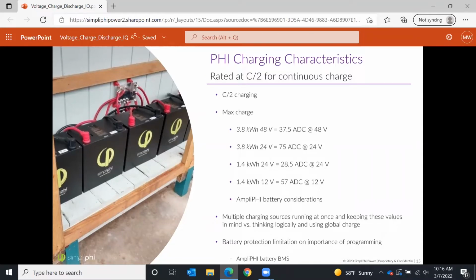Another thing to keep in mind when talking about charging is multiple charge sources. If you've got an 80 amp charge controller and 3 batteries, that's totally fine, there's no way your charge controller can charge those batteries too quickly. But if you've got an 8 kilowatt inverter with a generator charging at the same time, it's going to be charging too quickly.